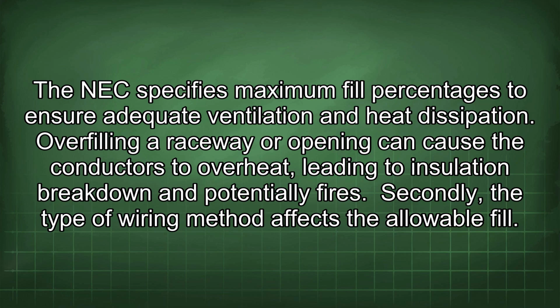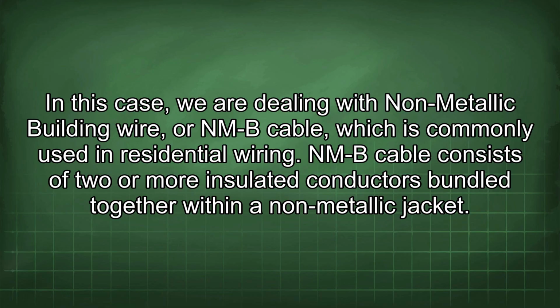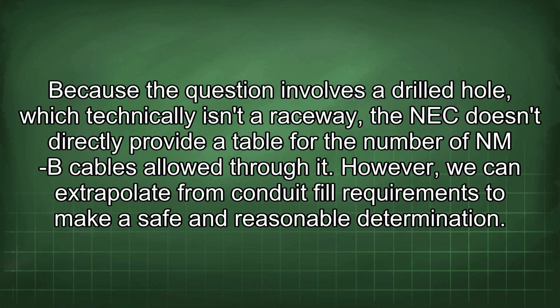Secondly, the type of wiring method affects the allowable fill. In this case, we are dealing with non-metallic building wire, or NMB cable, which is commonly used in residential wiring. NMB cable consists of 2 or more insulated conductors bundled together within a non-metallic jacket. Because the question involves a drilled hole, which technically isn't a raceway, the NEC doesn't directly provide a table for the number of NMB cables allowed through it. However, we can extrapolate from conduit fill requirements to make a safe and reasonable determination.